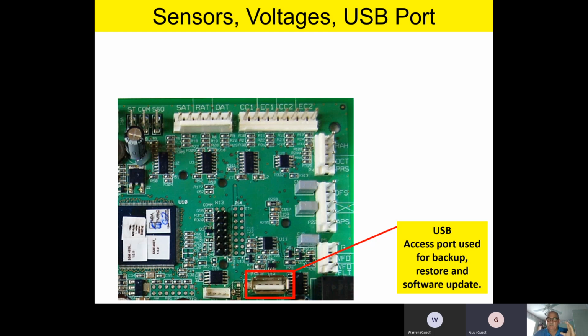I believe if you get a replacement board, if you have to warranty the board out, the replacement board is a universal board, which is going to be two-stage. Depending on the unit, you'll basically have a customized board for that unit, single-stage or two-stage. But if you buy a replacement board, you may notice that there's more relays on it that just aren't used. So instead of making 57 or 100 different replacement boards, they make essentially one replacement board that'll work on anything, if that makes any sense. Good, excellent question. Any other good questions?